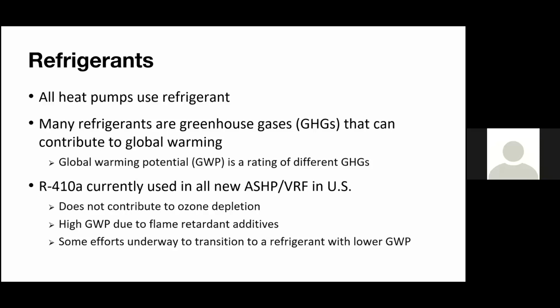Of course, we don't want to put the refrigerants in the air. We're trying to keep them inside the machines, but eventually there could be leaks. If they're not recycled properly, they could end up in the atmosphere. So there are concerns out there around these refrigerants and how to reduce their global warming potential. There are currently no phase outs in the US at the federal level for R410A when it applies to air source heat pumps or VRF.